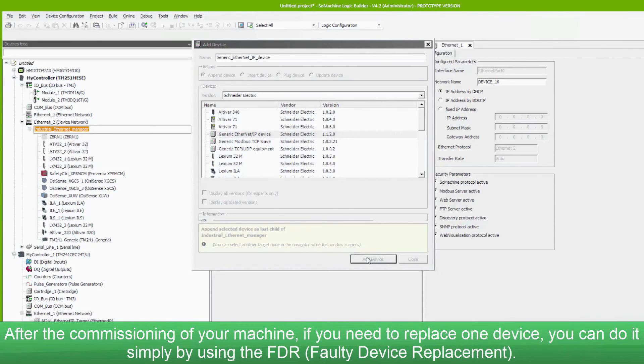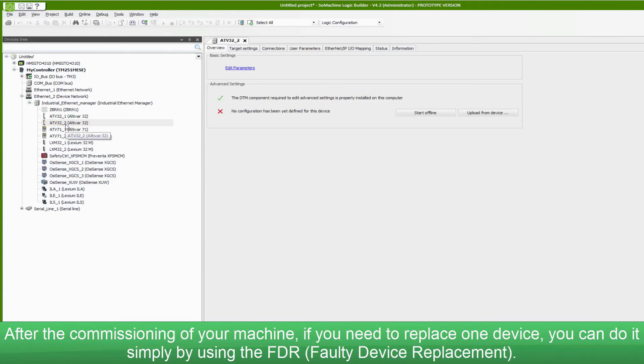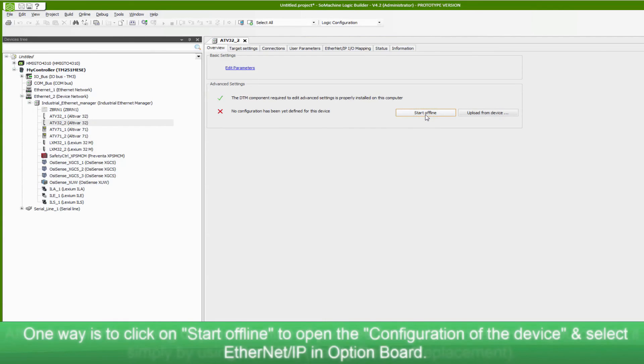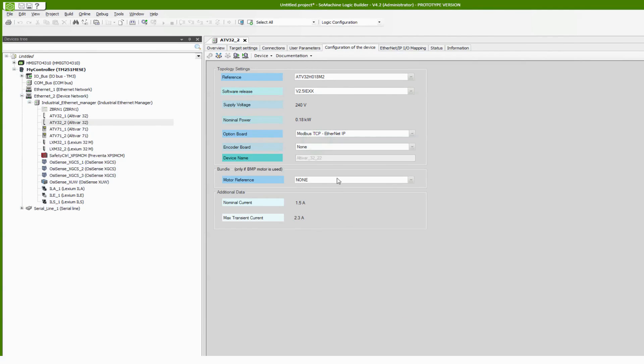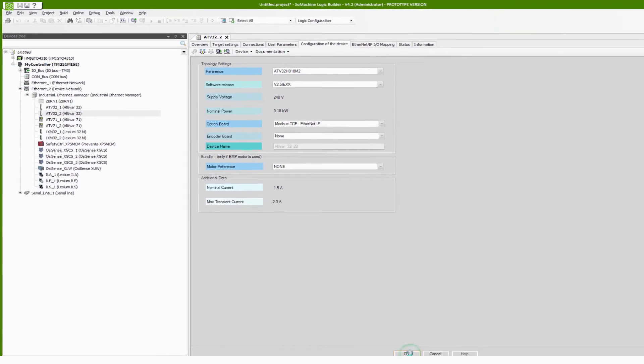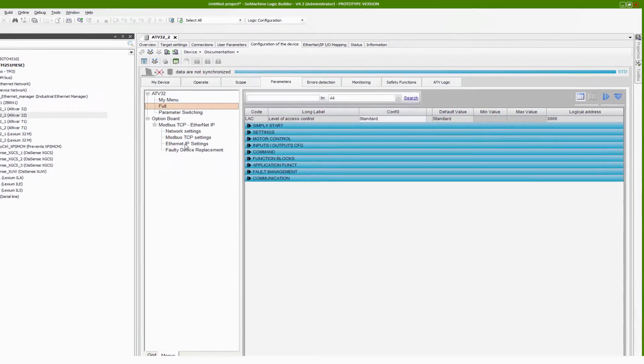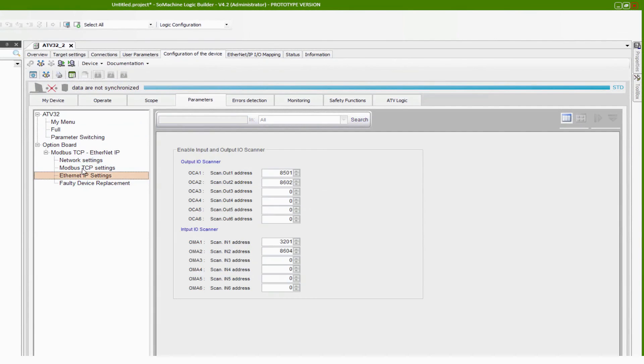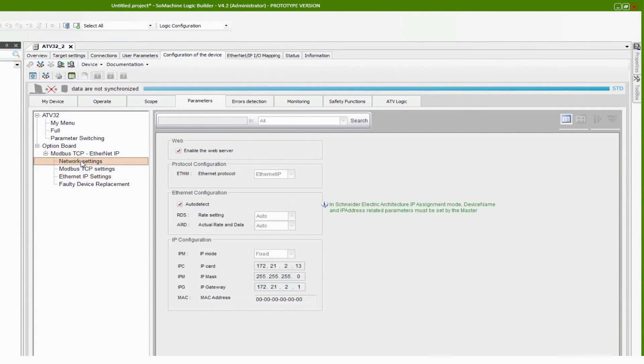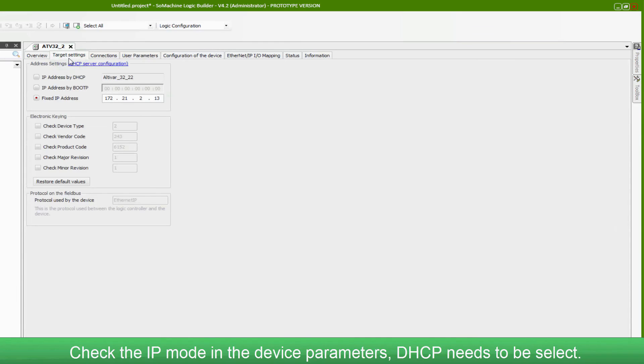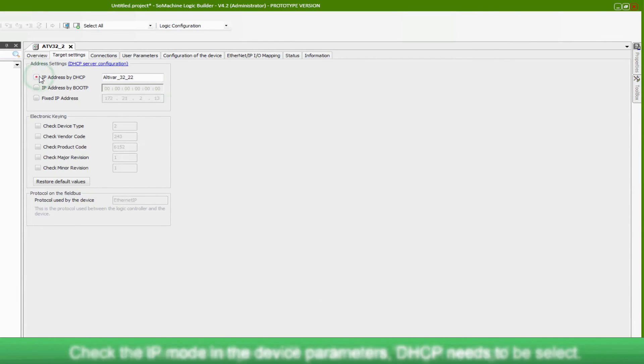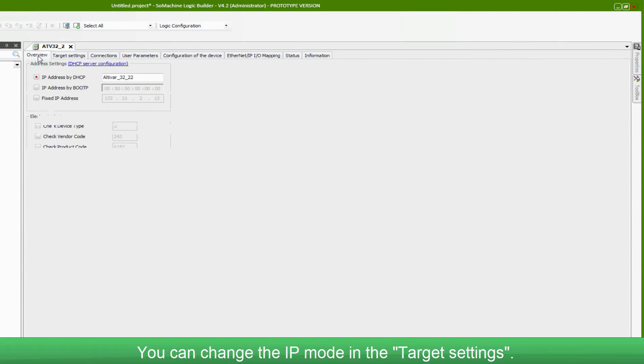After the commissioning of your machine, if you need to replace one device, you can do it simply by using the FDR faulty device replacement. One way is to start offline to open the configuration of the device and select Ethernet IP in option board. Check the IP mode in the device parameters. DHCP needs to be selected. You can change the IP mode in the target setting.